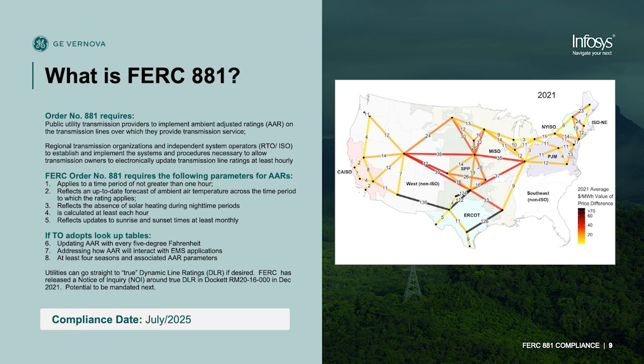So this limiting of the capacity on the system has unnecessarily driven up the congestion costs of transmission across the United States. And so FERC has made an order mandating that you have to have, at a minimum, ambient adjusted ratings implemented as a transmission owner. So that means that for minimum compliance, you would need to have 5-degree incremental rating sets, 5-degree Fahrenheit incremental rating sets across your footprint that reflect at least hourly the temperature change.